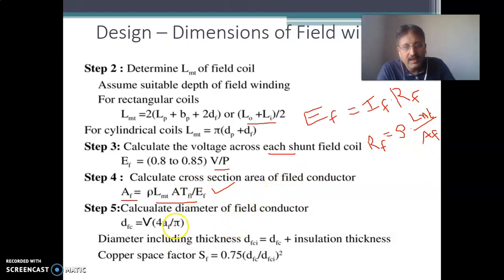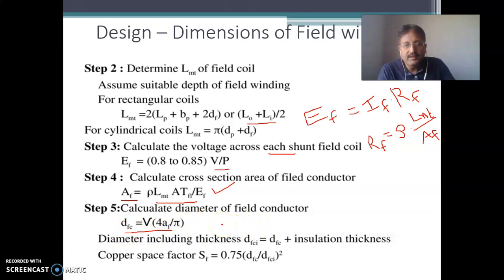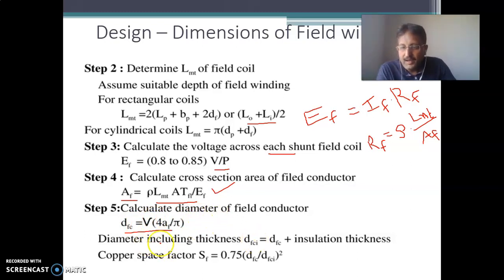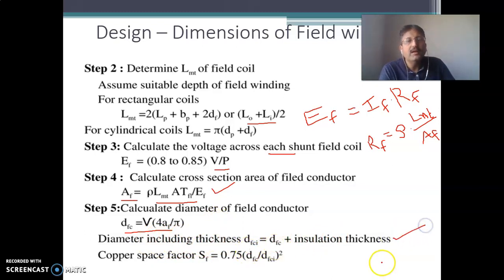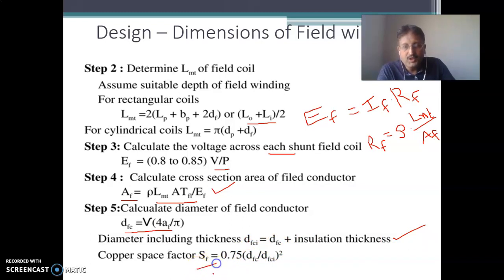Once you get the area AF, assuming the conductor is circular — area = (π/4)d² — you can find the diameter as the square root of (4A / π). You also need to consider the thickness of insulation, so this diameter includes the insulation thickness. Also consider the space factor, which is 0.75.